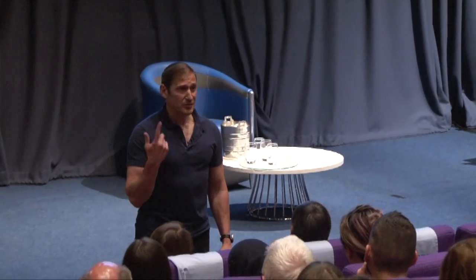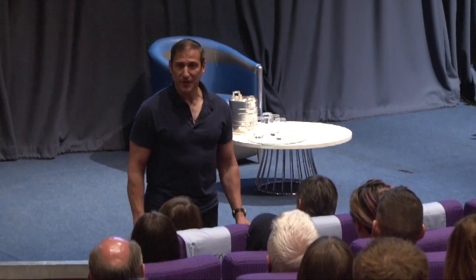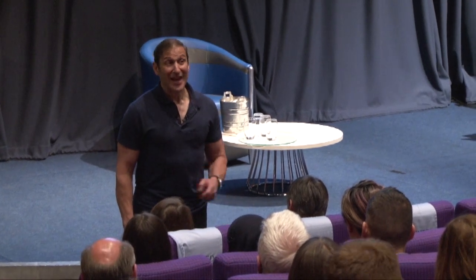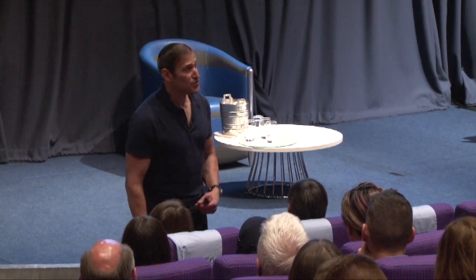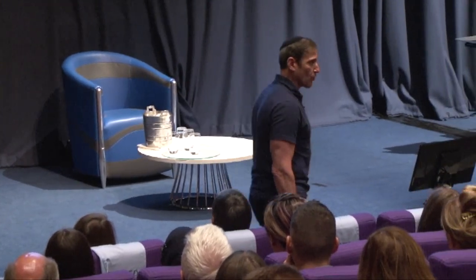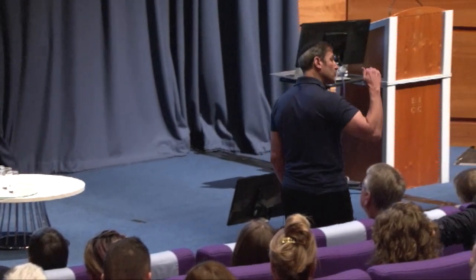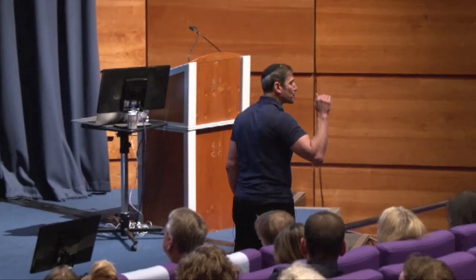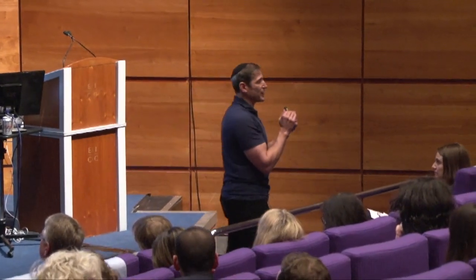What is considered a risk, and what we're actually trying to regulate for, is cardiac stimulation. That we would not want. Cardiac stimulation, we give another word to, we call that an arrhythmia. So arrhythmogenesis, inducing an arrhythmia, is what we're actually attempting to avoid. And thresholds are meant to regulate the chances of causing peripheral nerve stimulation. Because if you don't cause PNS, you're not going to cause cardiac stimulation. And so you will find regulation here regarding the chance of causing peripheral nerve stimulation.